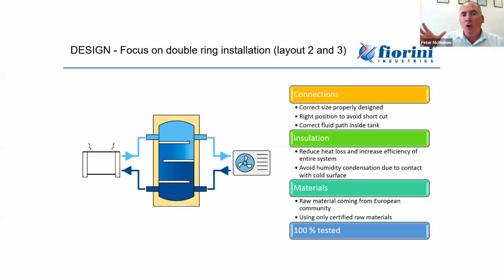Quite simply, they got a big oil storage tank, put it in this attic space I climbed up to have a look at, and they had located the outlet from the tank very close to the return back into the tank. And they've done the exact same on the far side. And as you can imagine, both circuits were simply short circuiting. So the positioning of your connections on buffer tanks, maybe with baffle plates or sparge pipes, can all come into play.